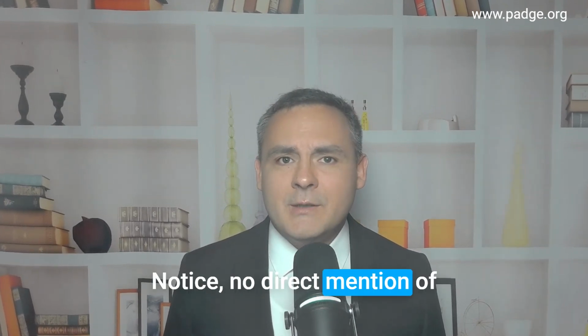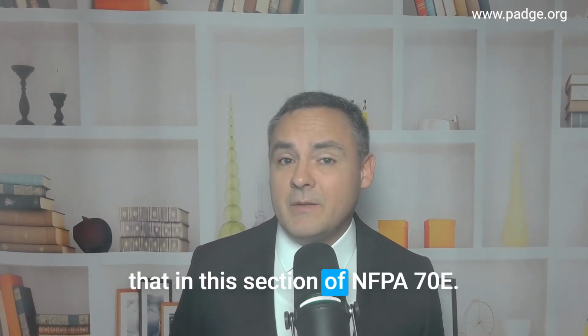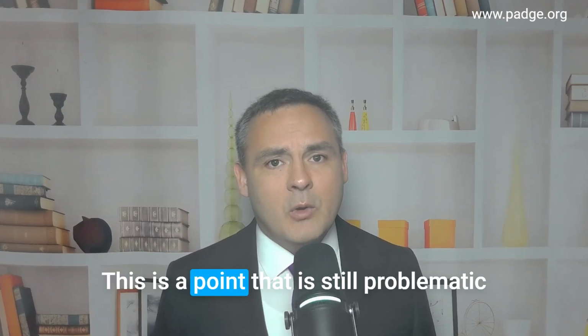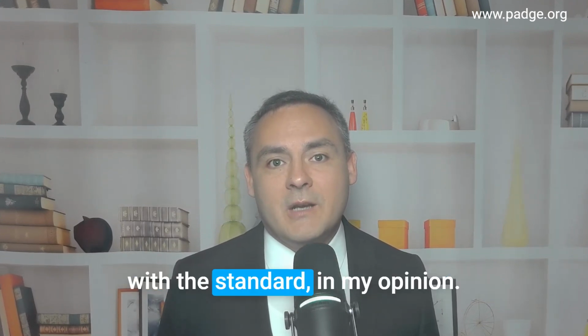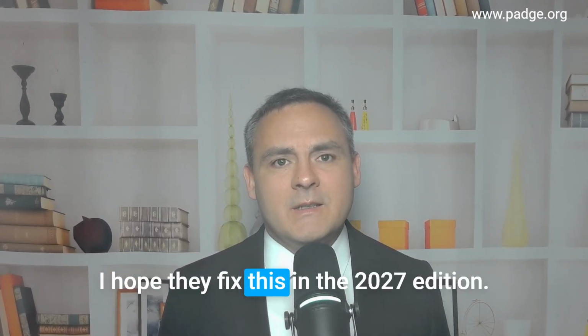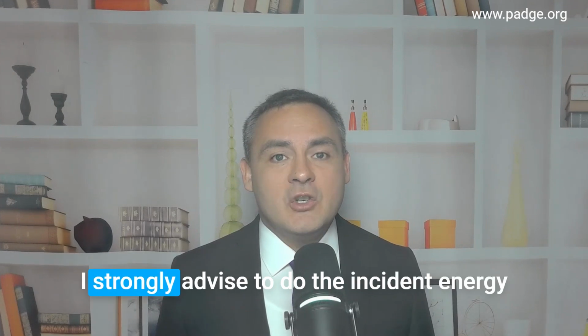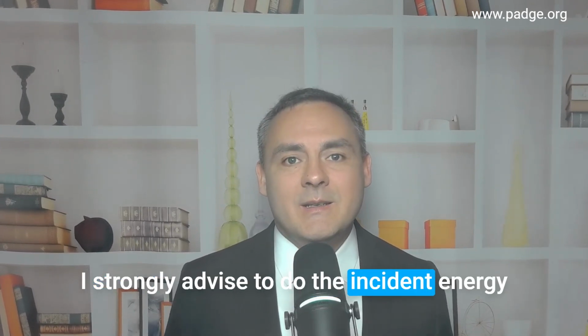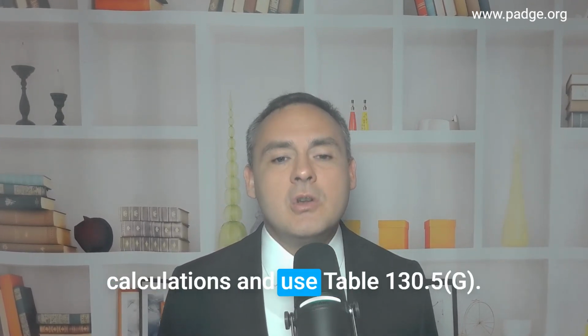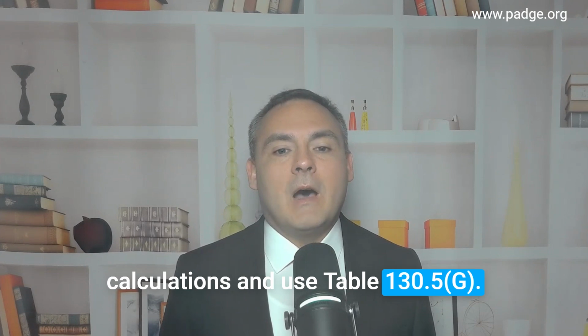Notice no direct mention of that in this section of NFPA 70E. This is a point that is still problematic with the standard, in my opinion. I hope they fix this in the 2027 edition. I strongly advise to do the incident energy calculations and use Table 130.5G.